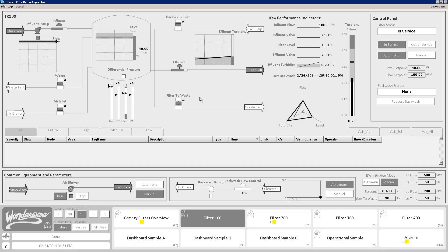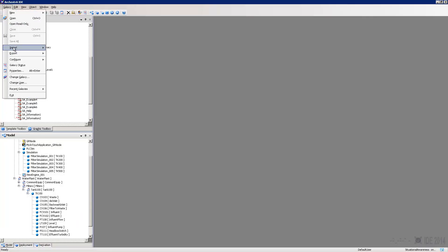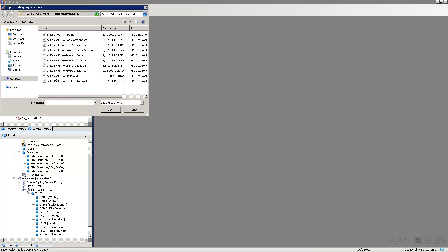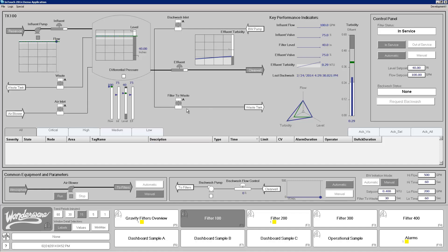There can be things done to be more visually appealing, and that's where we get into some of the issues in the marketplace with color recommendations. Some say go straight grays and only deviate when drawing the operator's attention. Others say you can utilize alternate colors. I'll demonstrate by importing a palette to change out my entire styles. You'll notice there's still a lot of gray, but now actual values are appearing more in blues, set points are in greens — I've leveraged some extra colors.